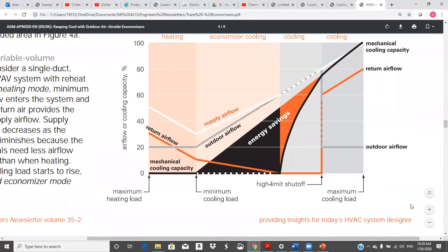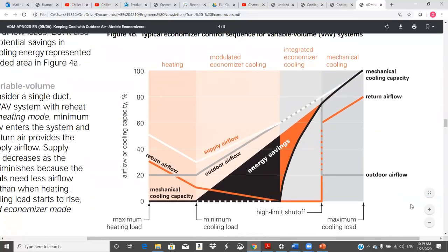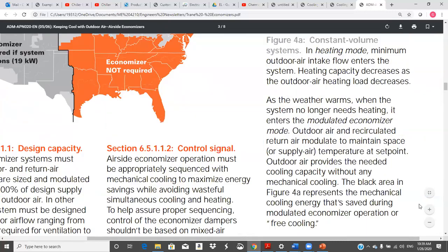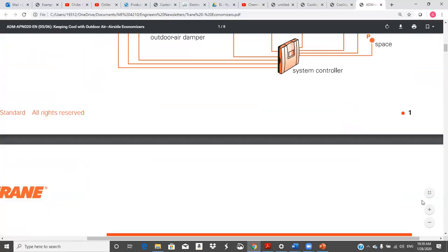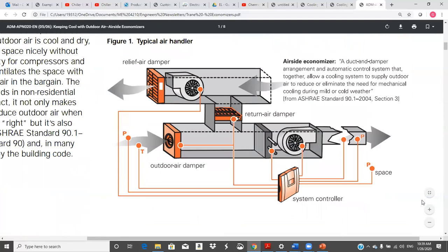Sometimes I have to go review these things. This is a variable air volume system. Okay, so let me talk to you a little bit about that. What this VAV system does, and this isn't a terribly good diagram for it, but this is a supply air duct. So I've got my 56-degree air, and it's going down here. I get down here to the first office, and it goes into what's called a VAV box. And a VAV box is just a variable volume damper.